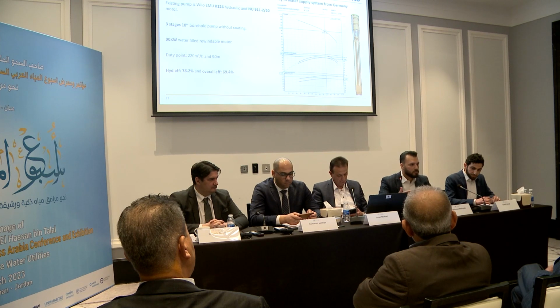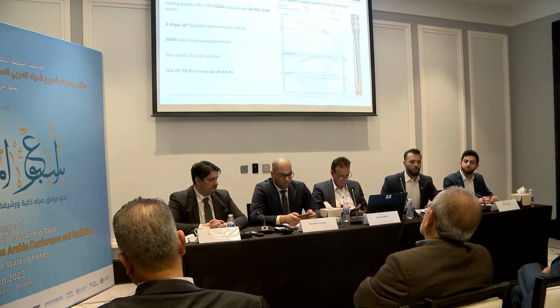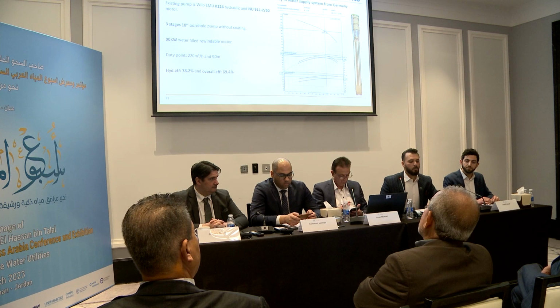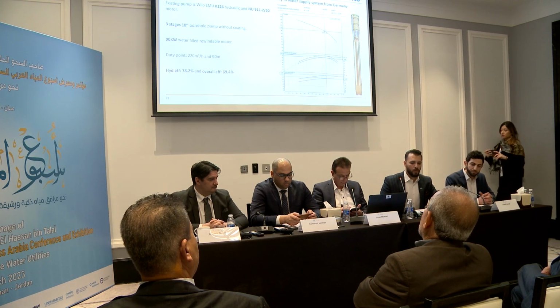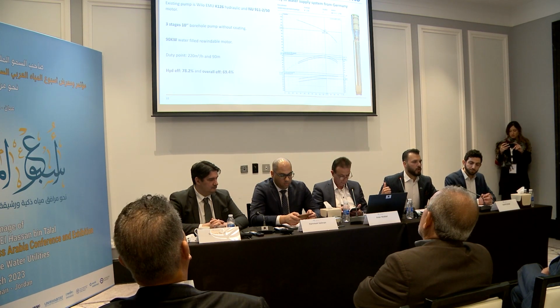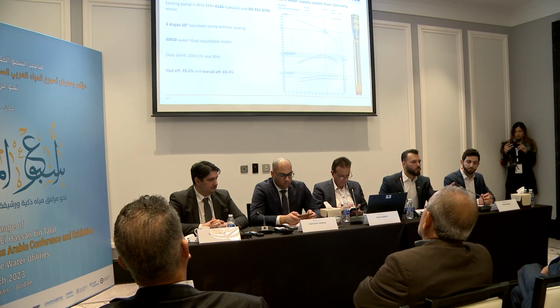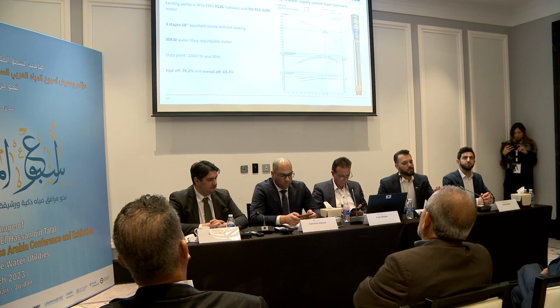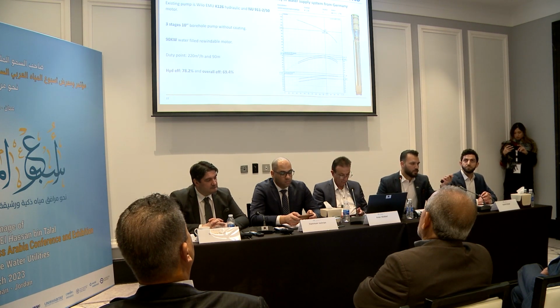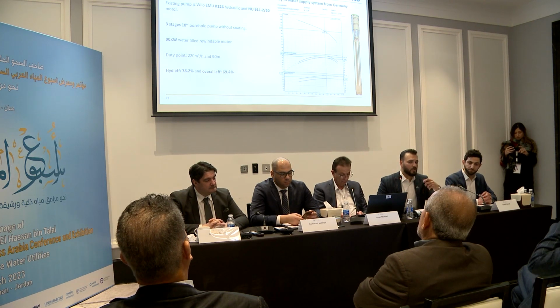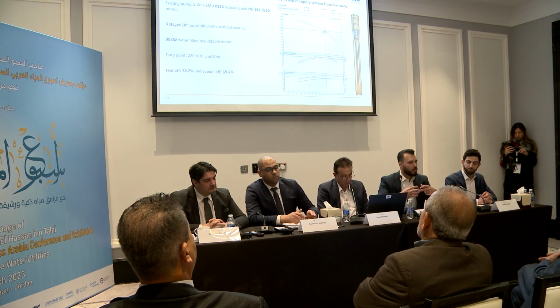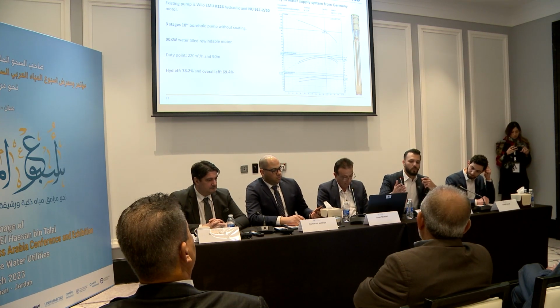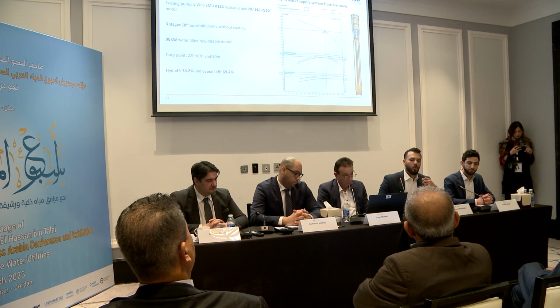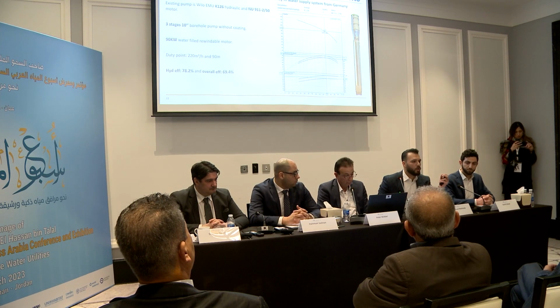Taking a live example of this, we have a pump station in Germany which was replaced with higher efficiency pumps. The existing pump was also from Wilo, but an old one, operating duty point 220 cubic meters per hour at 90 meter head. This pump had a 90 kilowatt motor and a hydraulic efficiency of 78%, which is usually a good efficiency compared to a semi-axial impeller for borehole pumps. So you end up with an overall efficiency for the pump and motor of 69.4%.